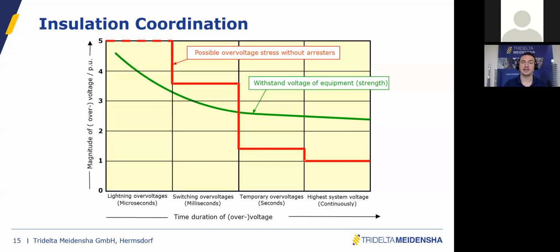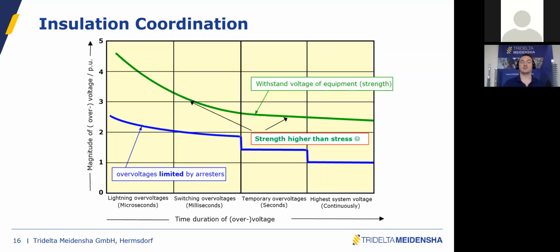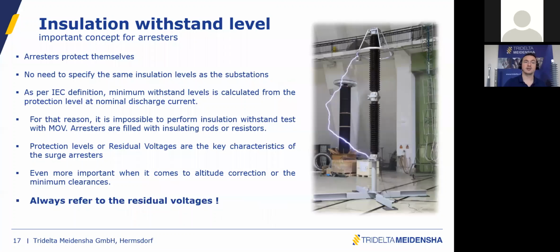As you can see, they can exceed the withstand voltage of the equipment. So you want to avoid that, especially if you have valuable equipment like power transformers. Therefore, by installing surge arresters, you have the possibility to minimize and control the stress. So when you define withstand level requirements, you always need to consider the protection level of the arrester. Otherwise, you will have a kind of oversized solution.